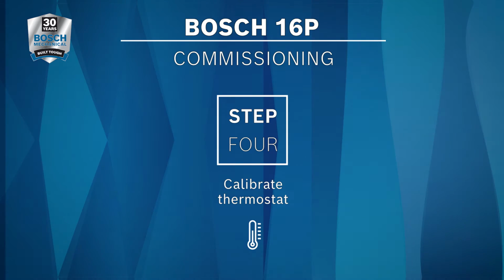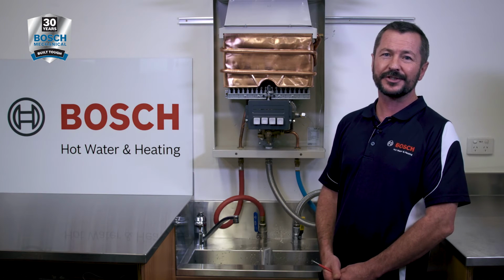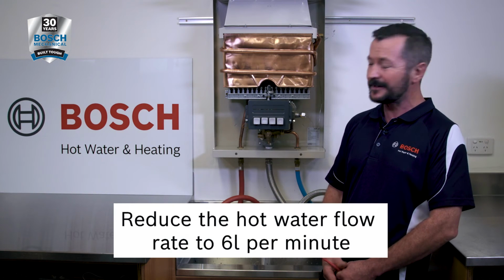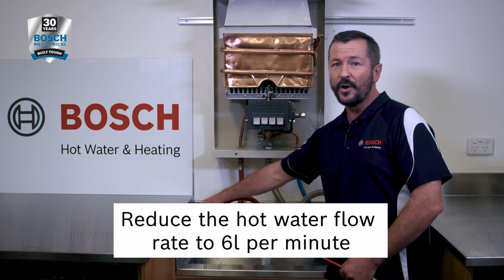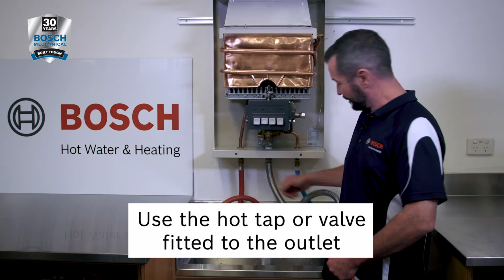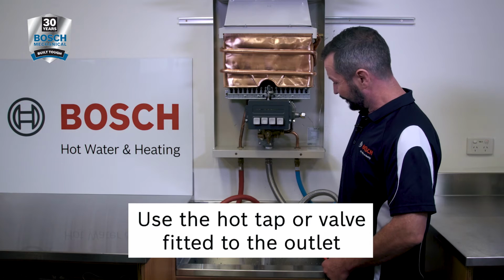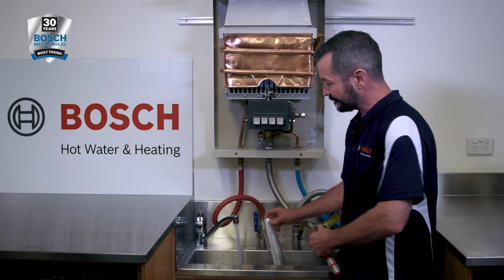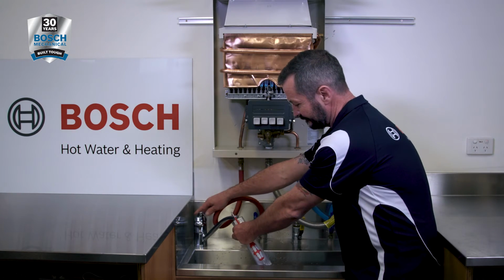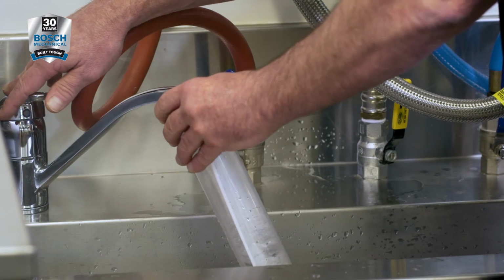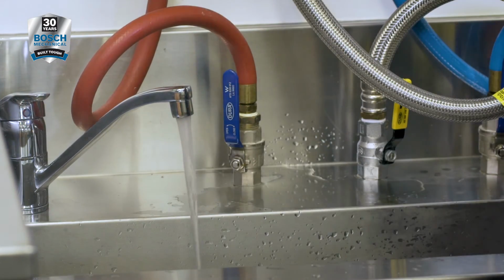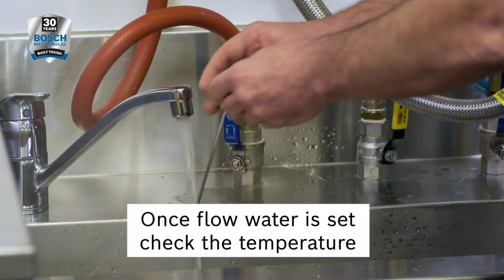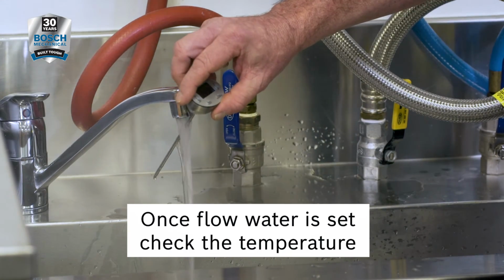Next step is to calibrate the thermostat. To do this, we start by reducing the hot water flow rate to 6 litres a minute by using the hot tap inside or the valve fitted to your outlet. Once we've got the flow rate to 6 litres a minute, check the temperature with your thermometer. What we're after here is 60 degrees.